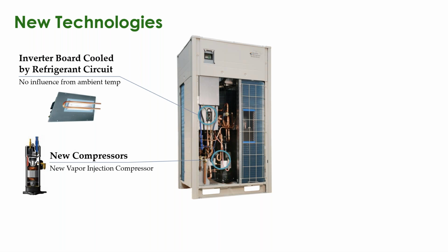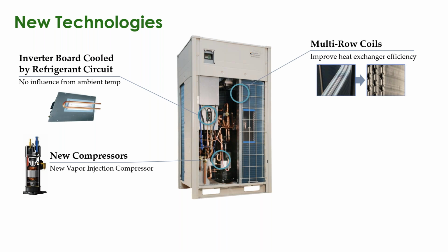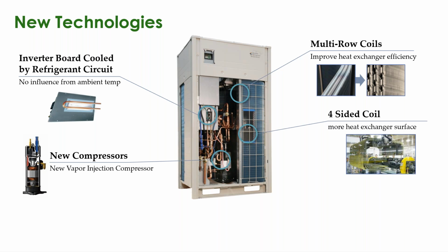New compressors have been added over the years, vapor injection compressors, which allow an improved discharge temperature by capturing waste heat off of the indoor coils and re-injecting it back into the compressor to increase the discharge temperature, adding capacity, as well as improve discharge temperatures off of the fan coils on the inside. Improved heat exchanger efficiencies with multiple row coils to maintain smaller footprints, and more heat exchanger surface, with most every manufacturer now running a 4-sided coil.